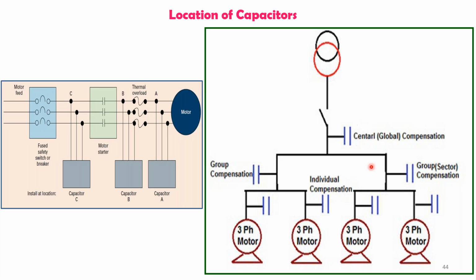Now, where do I have to place the capacitance? What is the ideal place to place the capacitance? This flow chart is always represented by BEE people, such that you can place your capacitor very near to the equipment. This is the first one, the individual compensation. Similarly, the difference in value will be compensated with the help of an SSB level as well as group compensation. And again, the difference between all the SSBs will be compensated at the central point where your APFC is going to be placed.